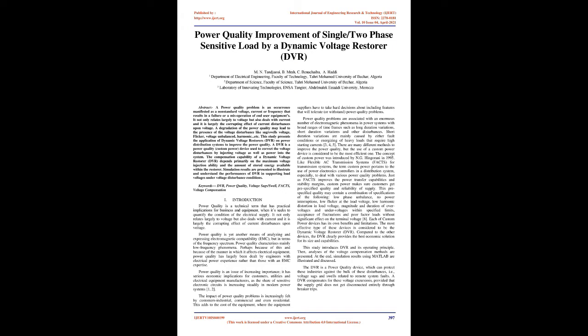Short-duration variations are mainly caused by either fault conditions or energizing of heavy loads that require high starting currents. There are many different methods to improve the power quality, but the use of a custom power device is considered to be the most efficient one. The concept of custom power was introduced by N.G. Hingorani in 1995.